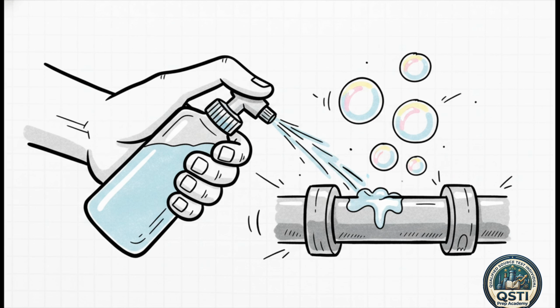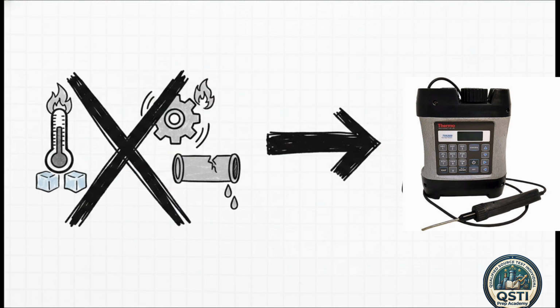Kind of amazing, right? However, this analog backup has some pretty strict rules. You cannot use the soap bubble method on equipment with continuously moving parts, like a rotating pump shaft. You can't use it if the surface temperature is below freezing or if it's above the boiling point of the soap solution, and obviously it won't work on large open areas or if the equipment is already leaking liquid. If any of those conditions exist, you are forced to revert immediately back to the high-tech instrument survey.